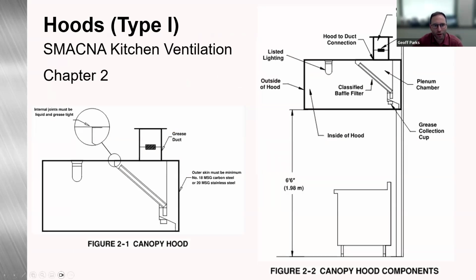Here I'm throwing up a couple details from the SMACNA kitchen ventilation. This is out of chapter 2, figure 2-1, canopy hood, and then figure 2-2, canopy hood components. Some components you might come across: baffle, filter, your grease collection, outside of your hood. So that's going to be your continuous welded. And then here we're showing a minimum height above the floor of 6 foot 6 inches. What we've put in the new release standard is we've kept the 6 foot 6 inches, but we added a note, as required by local code or something like that.